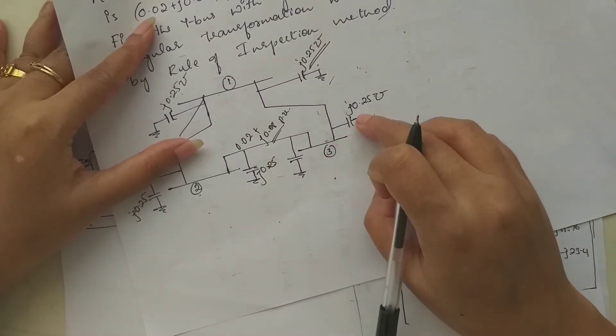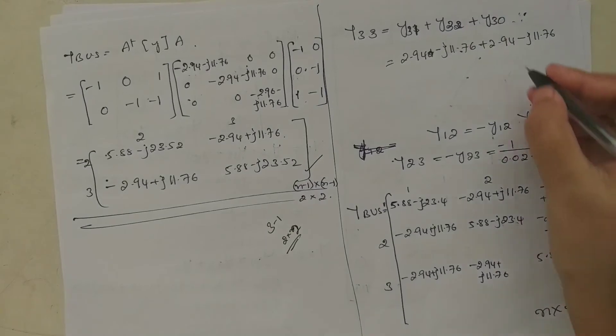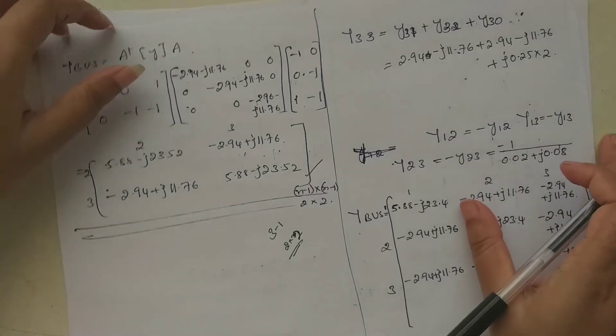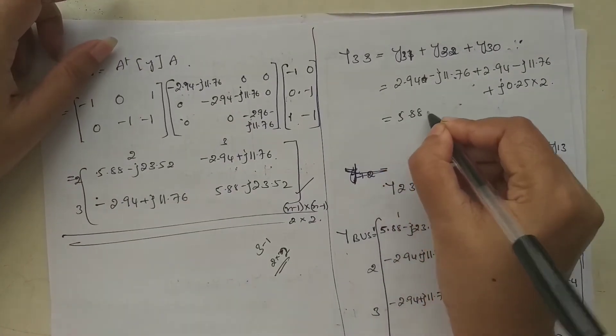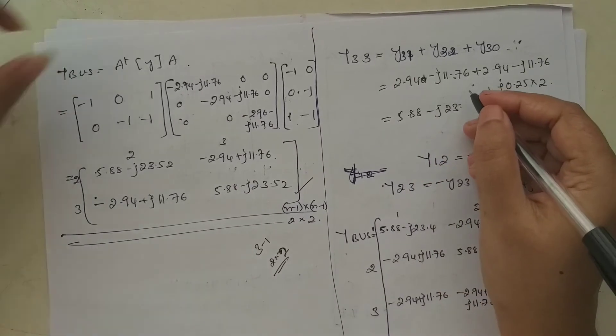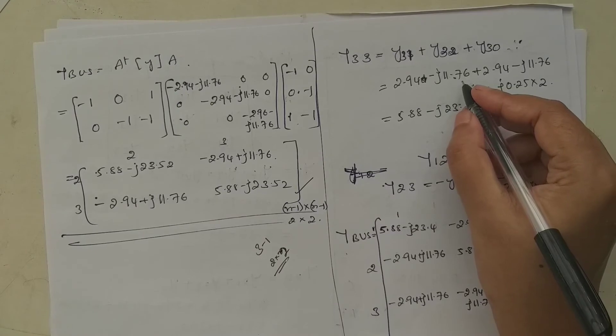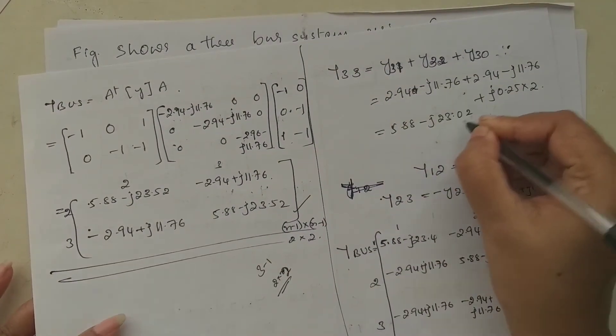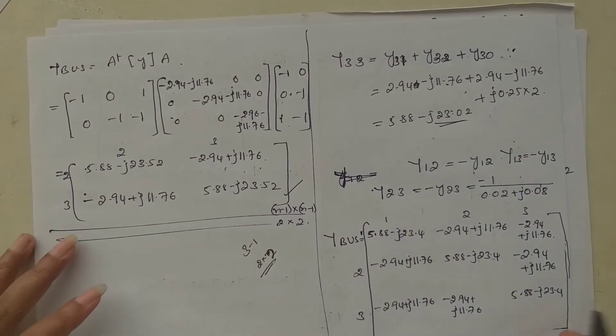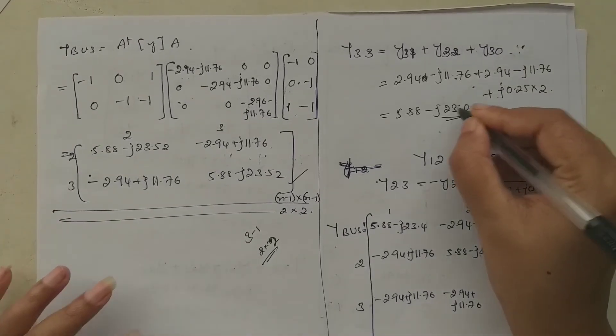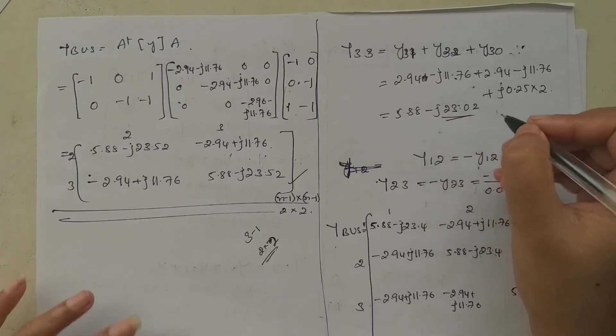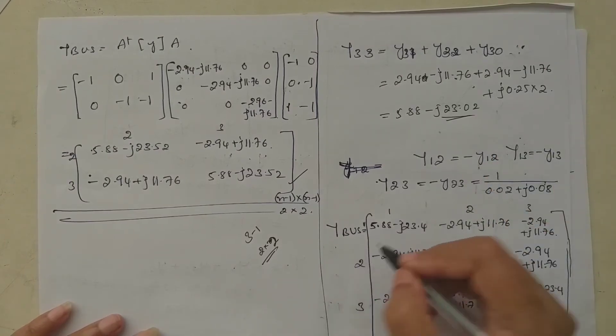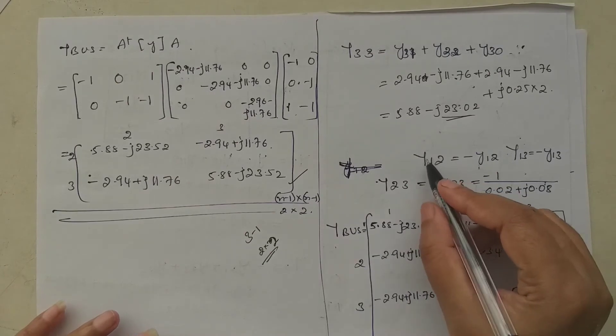For Y33: Y33 = Y31 + Y32 + Y30. Y31 = 2.94 - j11.76 and Y32 = 2.94 - j11.76. Looking at the diagram, node three also has half-line charging admittances of j0.25 on both sides, so Y30 = j0.25 + j0.25 = j0.5. Therefore Y33 = 5.88 - j23.02.